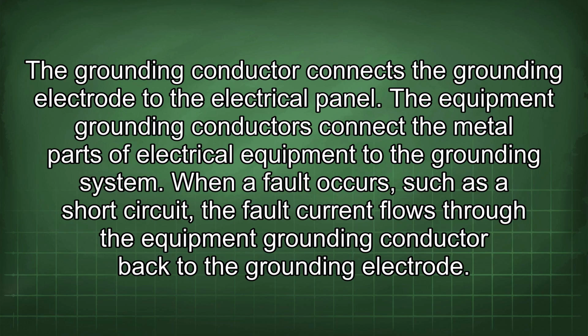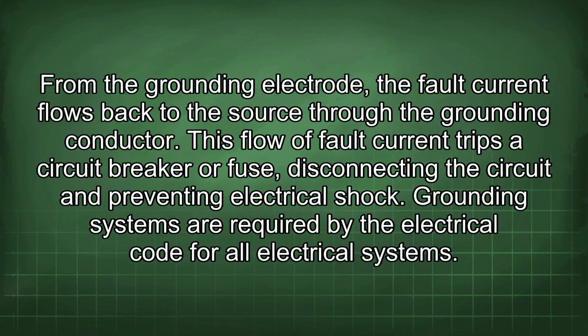When a fault occurs, such as a short circuit, the fault current flows through the equipment grounding conductor back to the grounding electrode. From the grounding electrode, the fault current flows back to the source through the grounding conductor. This flow of fault current trips a circuit breaker or fuse, disconnecting the circuit and preventing electrical shock.